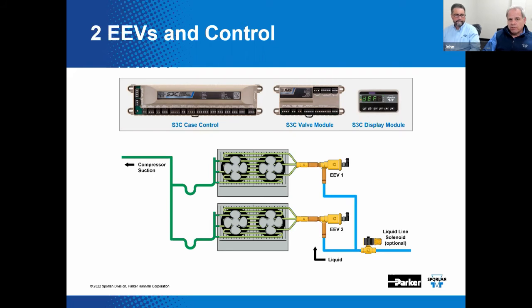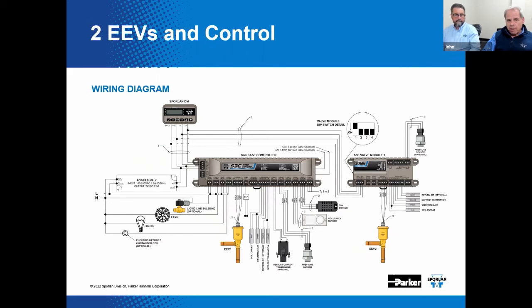Okay. In that case. Well, just for fun, let's look at the wiring diagram for this example. Here you got like we said, the valve module simply extends the input and output capability of a single case control. If you take a close look, you'll see EEV1 and the sensors and pressure transducer terminations made at the case control. Likewise, for EEV2, those sorts of things are terminated on it. And we've included the second pressure transducer here to show this option and how it will be terminated on the valve module versus 1 pressure transducer on, say, a common suction. So there's that second pressure transducer.